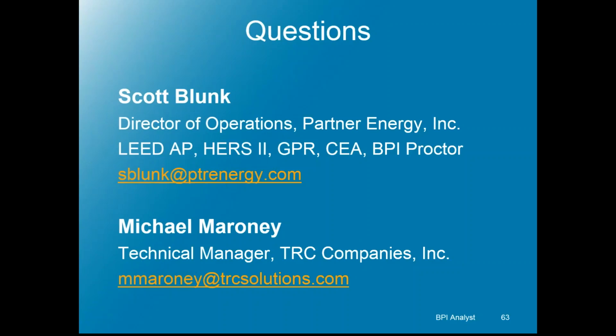Well, yeah, that's another good question, and again, it takes time. So the typical HVAC contractor, if you've got a 2-ton system, is going to sell you a 2-ton system because that's the quick thing. Unfortunately, the home was probably never sized to begin with. So if it had a 2-ton, it wasn't actually properly sized to begin with. So it could be undersized, but most likely it's oversized, as most systems are.